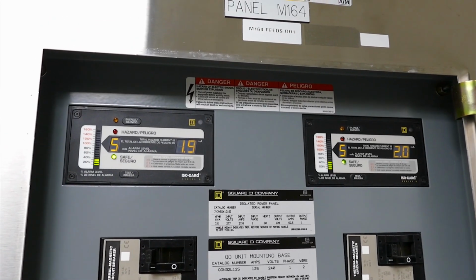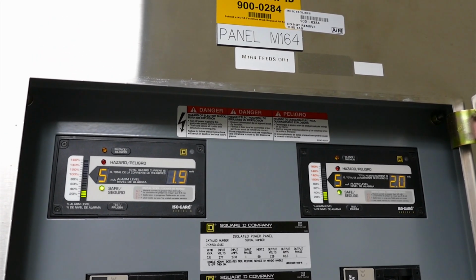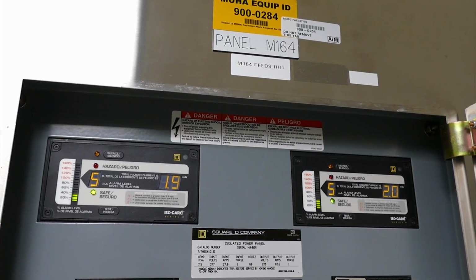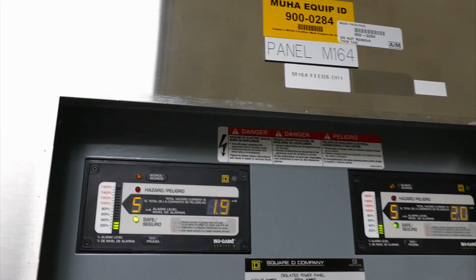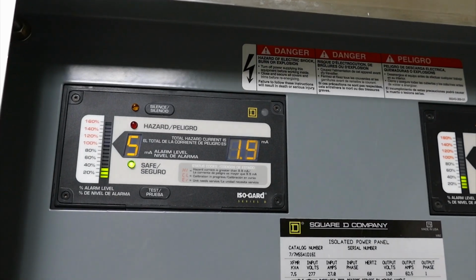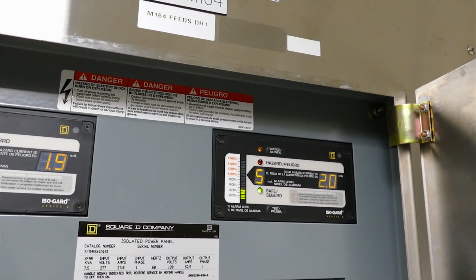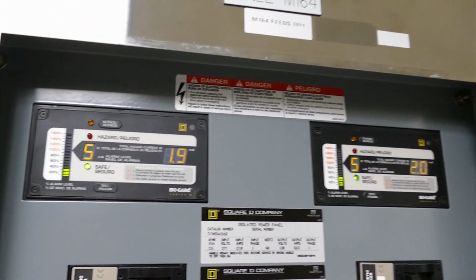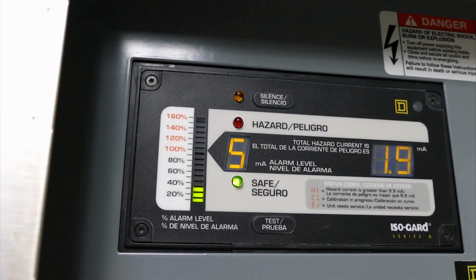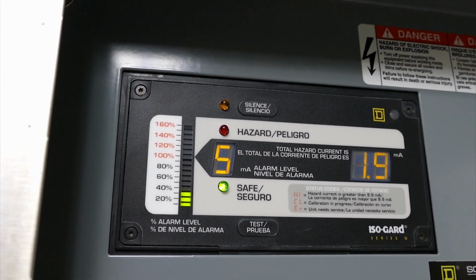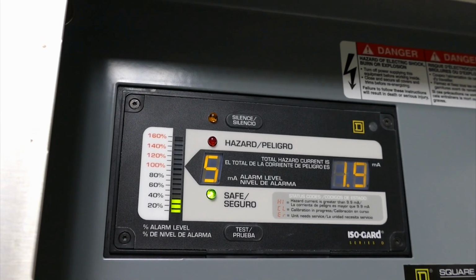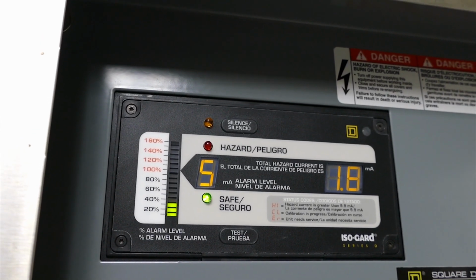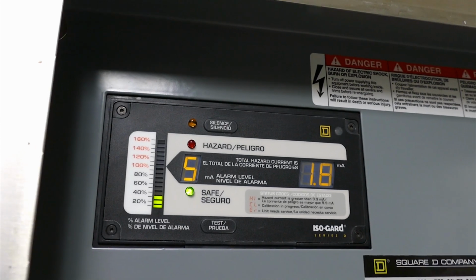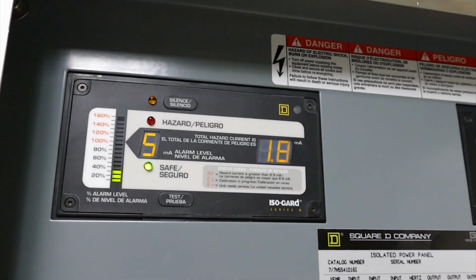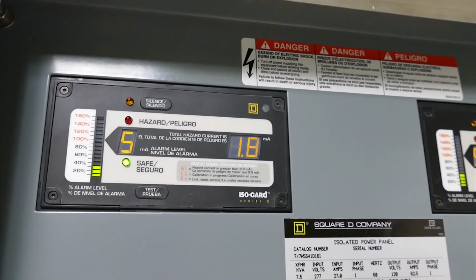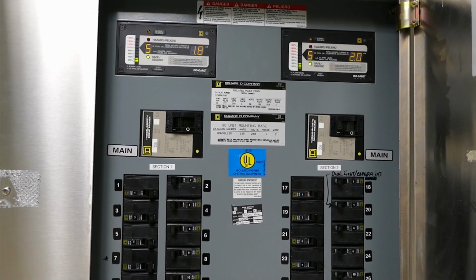What you have is these meters up at the top. They measure from the secondaries to ground, and they display the amount of milliamps of current. You can see right there it's 1.9 and 2 milliamps. Now if you look over here, you can see that it's barely loaded up. When it gets to 4.5, that's when it switches over to hazard. And when it hits 5 milliamps, which is the maximum amount, it will switch over and go to alarm condition. So that would be the line isolation panel.